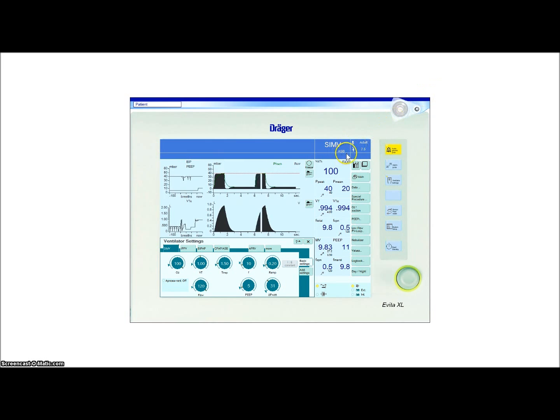ASB, as you see right here, is short for assisted spontaneous breathing. If we turn pressure support off, ASB is gone. You can still breathe, but it's going to be dead space, and it's going to feel like breathing through a straw. So therefore we have pressure support at 34.